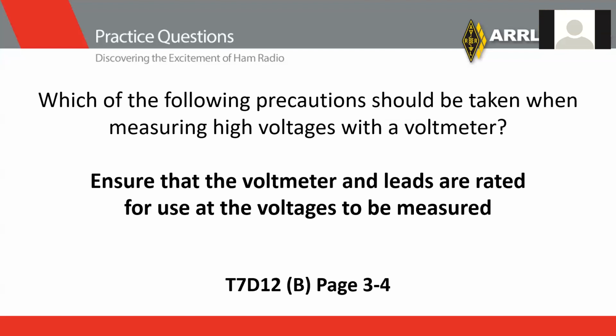What does the number on the plastic leads at the point of the wires indicate? It indicates that I need better glasses because I can't read them. Generally that's like 500 or 1,000 volts, and that's not enough - those little plastic tubes at the end of the leads have to be rated at the proper voltage too. Yeah, okay, it says 10 amps on the lead.